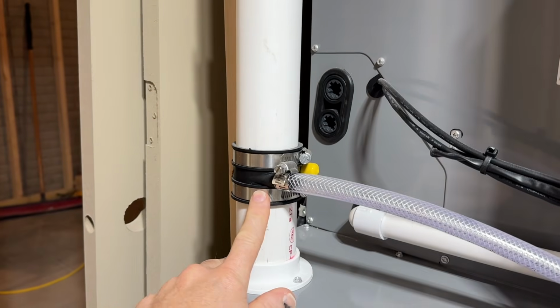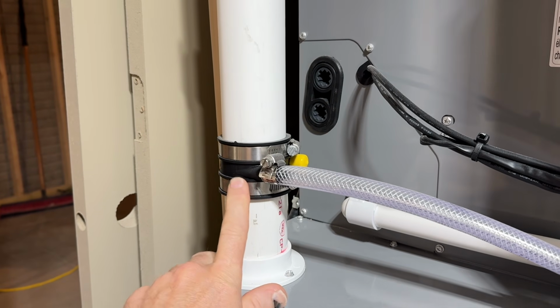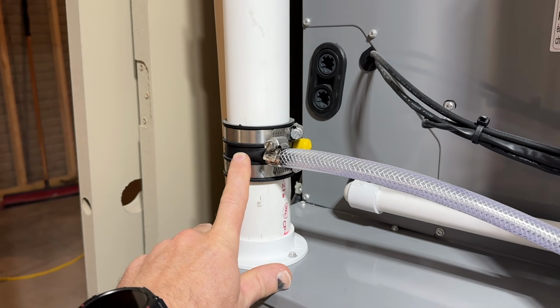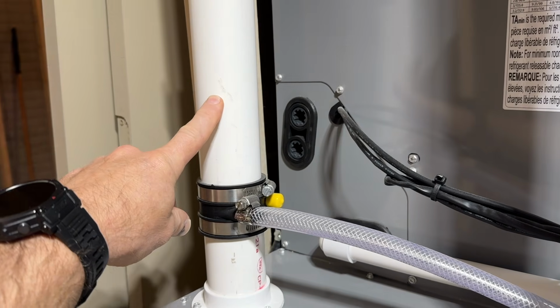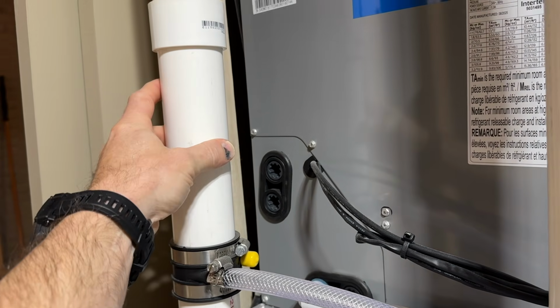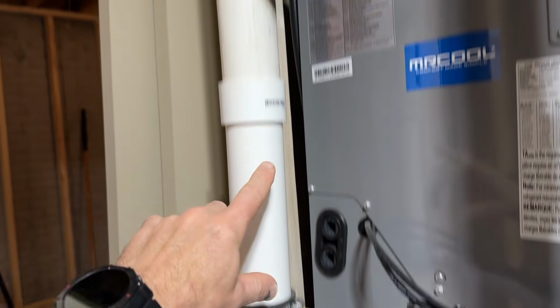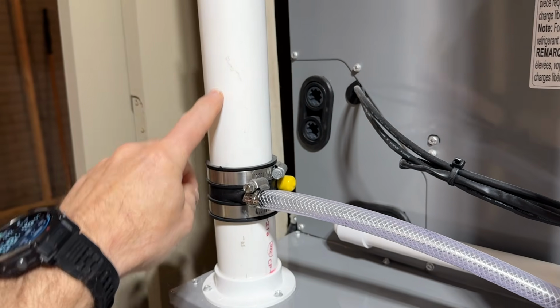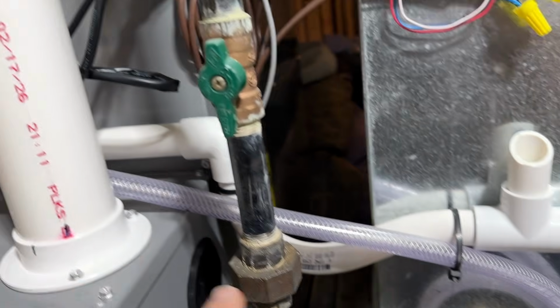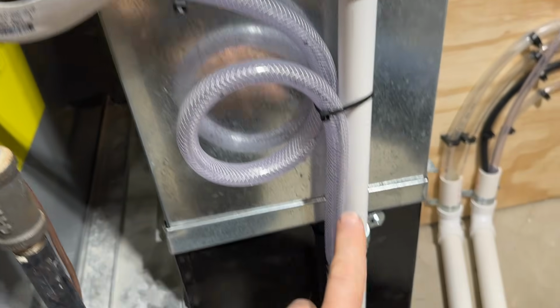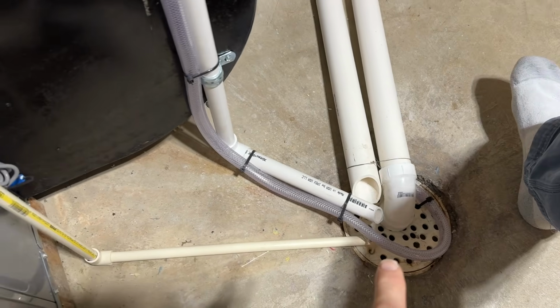And then one thing I like to do is on the intakes, I always put one of these condensate collectors. That way when you're pulling freezing cold air in and it's hitting, this is gonna be warm all the way to where it goes outside. It can condensate, so this will collect it, send it down, put a loop in it, kind of essentially like a trap, and then it goes out at the drain.